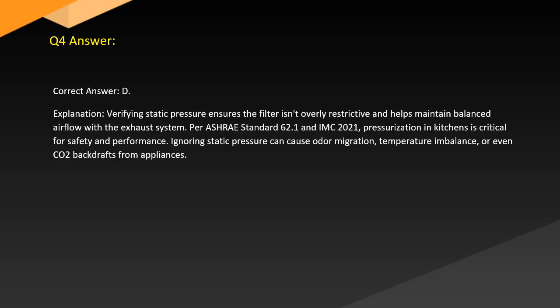Answer. Correct answer D. Explanation. Verifying static pressure ensures the filter isn't overly restrictive and helps maintain balanced airflow with the exhaust system. Per ASHRAE Standard 62.1 and IMC 2021, pressurization in kitchens is critical for safety and performance. Ignoring static pressure can cause odor migration, temperature imbalance, or even backdrafts from appliances.